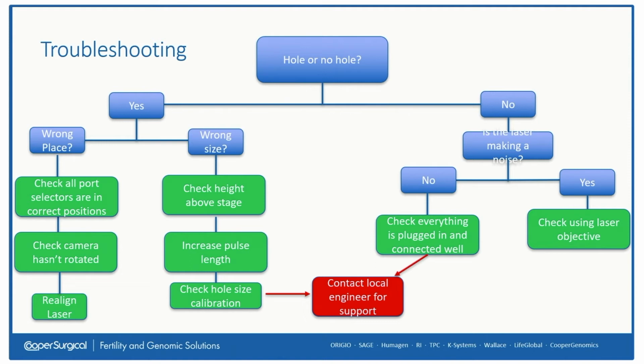So if there is a noise, the first thing to check is that you're on the correct laser objective. I know this sounds stupid, but the number of times I myself have made the same mistake, I really can't count. Then lastly, check that the pilot laser is still in the same location that the computer-generated target thinks it is. And if it is, and you're still getting nothing, then it's time to call your local support team in.